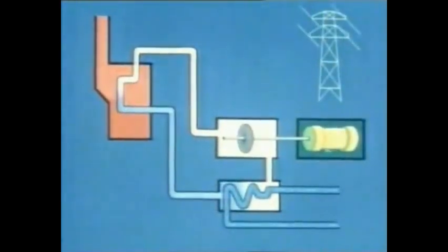We don't turn out anything like all the energy as electrical energy. A lot is unavoidably wasted as latent heat in the conversion back to water, but it's made as efficient as possible. Air is needed to burn the coal. It's drawn in from outside, and here's one of the huge ducts down which it comes. Each of the 4 boilers has 2 furnaces, supplied with air in this way.